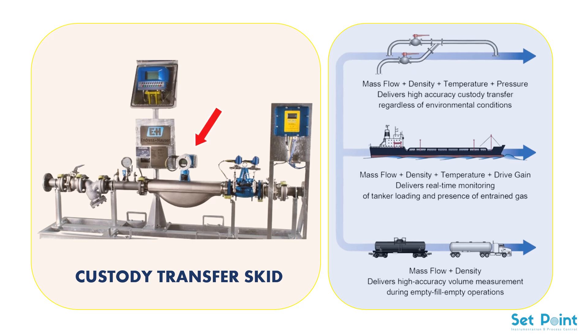This system uses a mass meter so that the client can distinguish between two different products via the same stream. Mass flow meters measure the mass of the fluid being transferred by measuring the vibrations in the tubes caused by the Coriolis force. The total volume can be found using the total mass transferred and the density of the fluid.